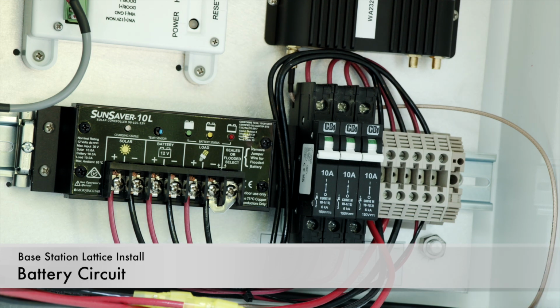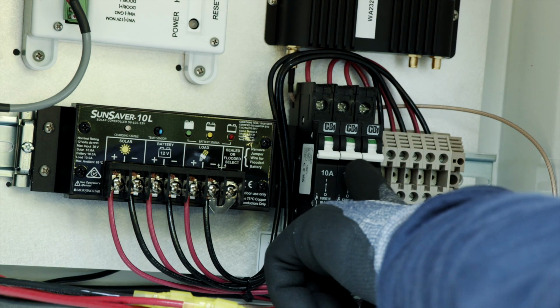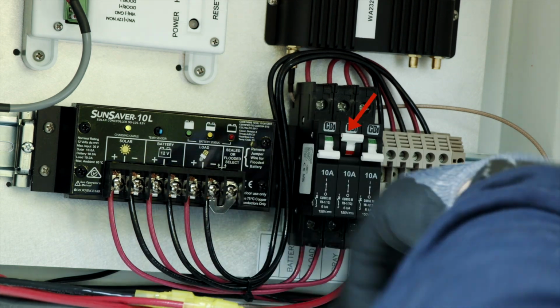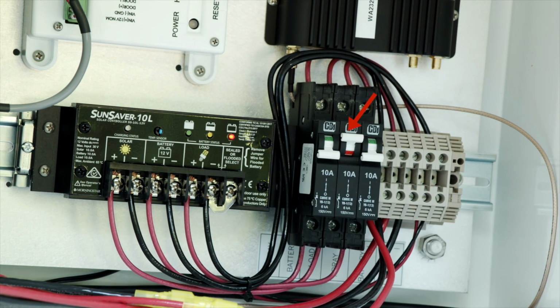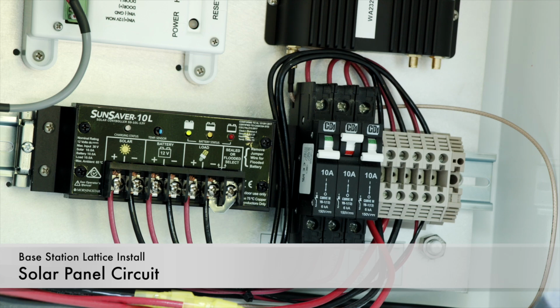Battery circuit. Locate the 3 breakers inside the cabinet. Switch on the center breaker for the battery connection. Wait for 10 seconds, allowing the solar controller to power up. The battery status LEDs on the solar controller should be either green or yellow, showing the state of charge of the battery.